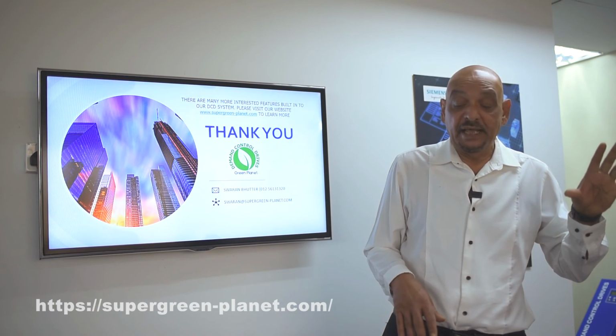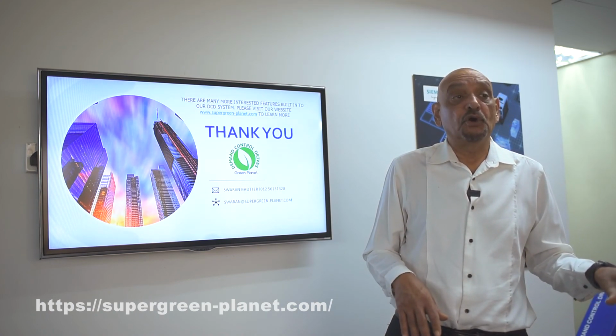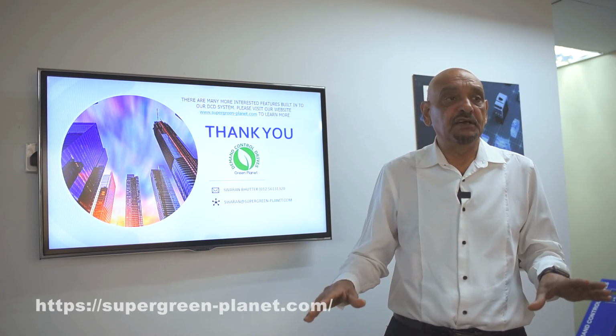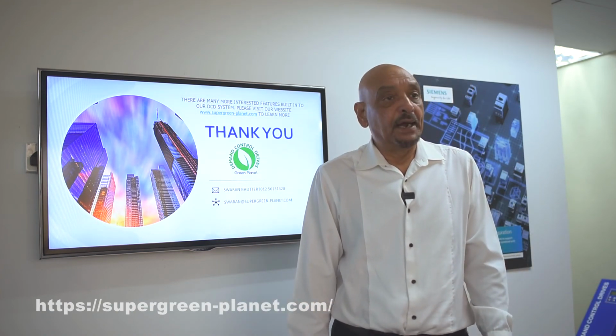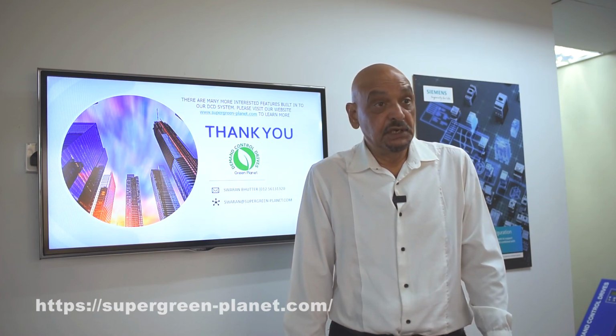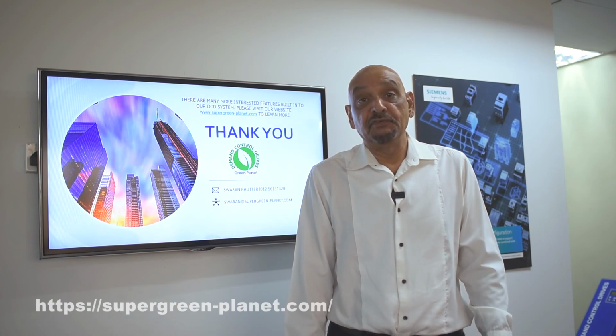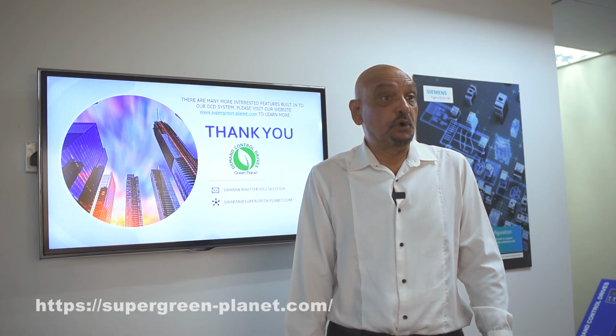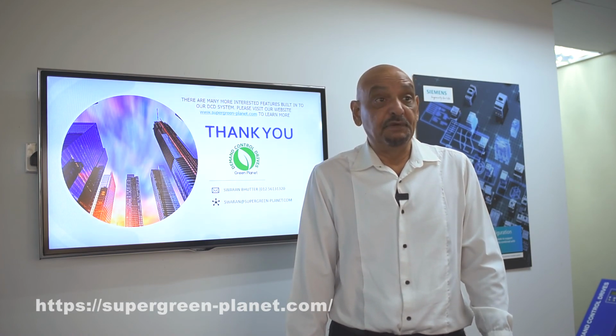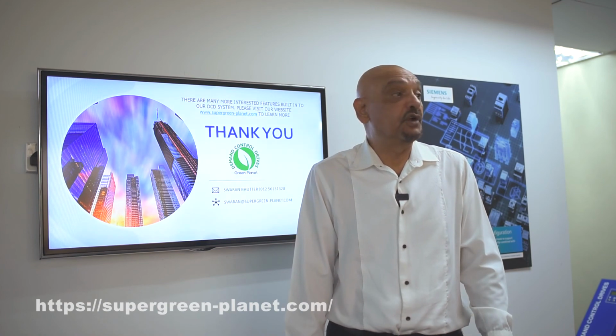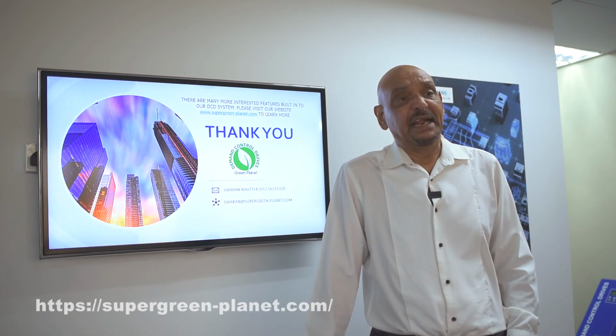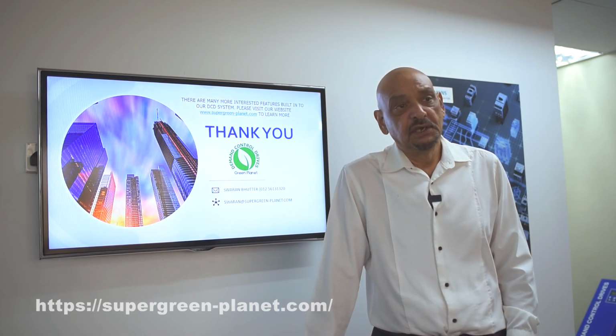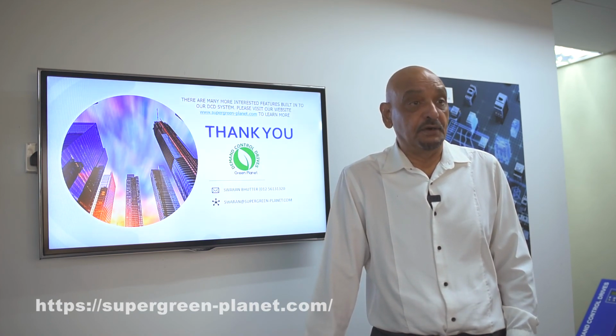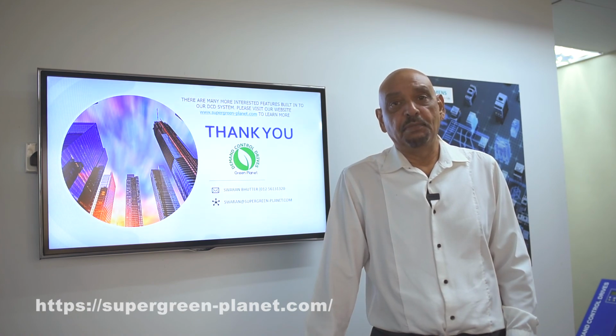Now, whatever performance is now done by your existing mechanical control panel is taken over by solid state electronics, which means that if you were to install our DCD, you not only get a very fast return on investment, you're going to get a brand new control panel. Your current control panel may be 15 years old, 20 years old, and this is where most of your maintenance cost is. You get breakdowns like, for example, your contactors, your timers, your MCBs, which is all gone now. With solid state electronics, you don't have all these breakdowns.